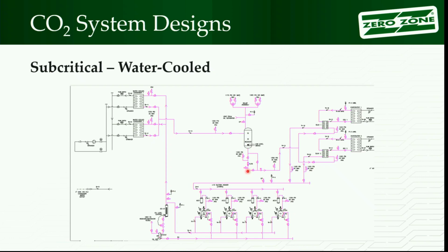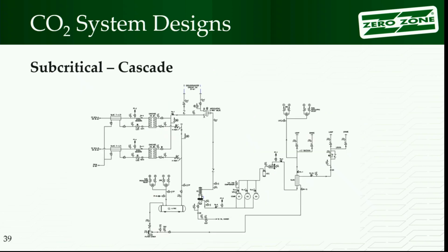Nowhere in the system, unless there's a fire in the building, will you ever get a high enough pressure to cause a relief valve to go. It doesn't happen. So we do that. It's more for industrial customers, not so available on the commercial side. Our display cases are 650, 700 pound coil design. Really 90 bar coils don't exist, so you get it more in the industrial application where you can buy a little higher pressure evaporators.